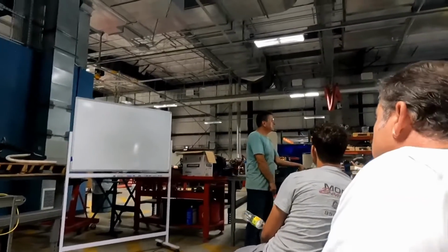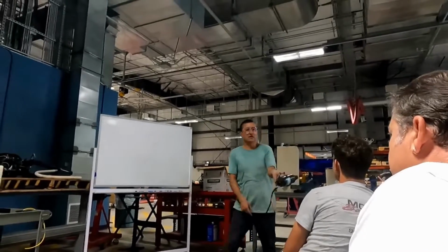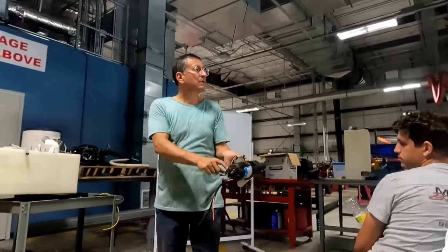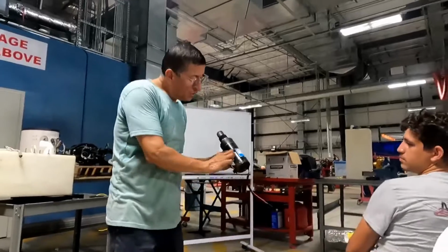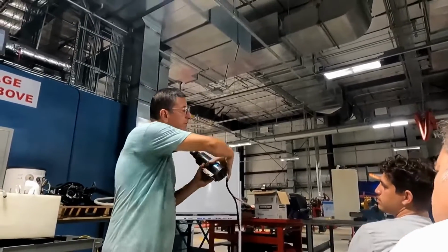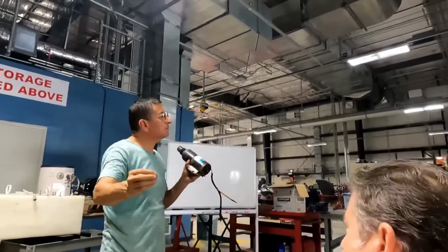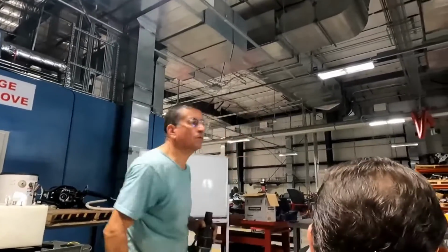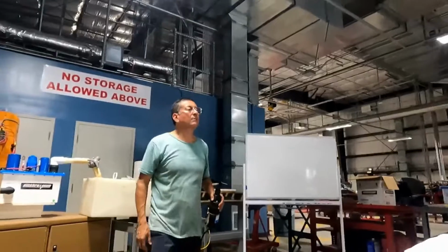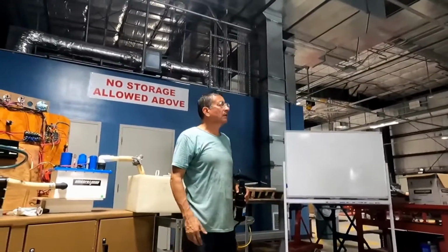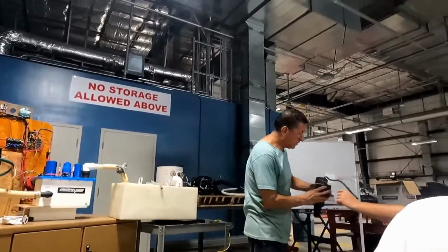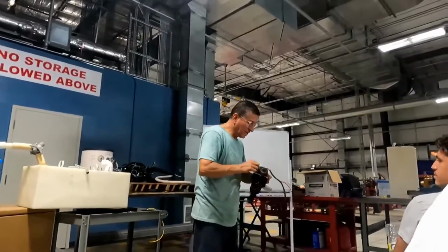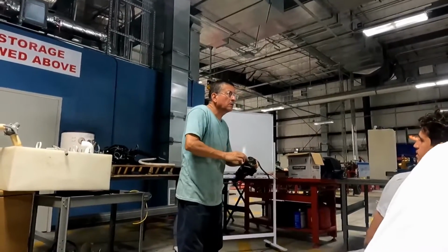You see? Don't bond the DC, and this is the consequence. You need one cable here from the case into the bonding system. So where do you put it on that one? That's correct. This is a freshwater pump. Exactly the same, because it's not bonded. Where do you ground it on that one? Because all those screws are going to be... Okay, look at this. Here on those screws.